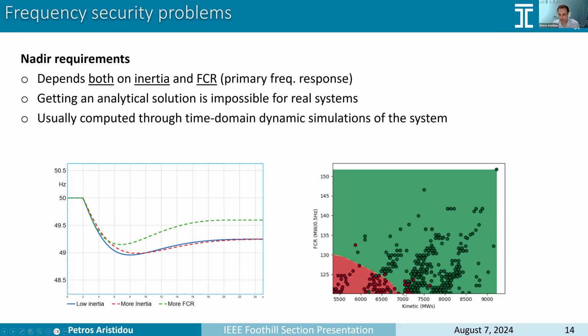And some of you might ask, why is that the case? The reason is that the nadir does not depend only on the amount of frequency containment reserves that we have, but also on the activation speed of the generator. So if we have committed generators that, for example, are gas turbines and are faster to react, then we might have lower inertia and lower frequency containment reserves, but still be secure in terms of nadir. But if we have slow generators, then even with higher amounts of frequency containment reserves and higher amounts of kinetic energy, we can still be not secure.